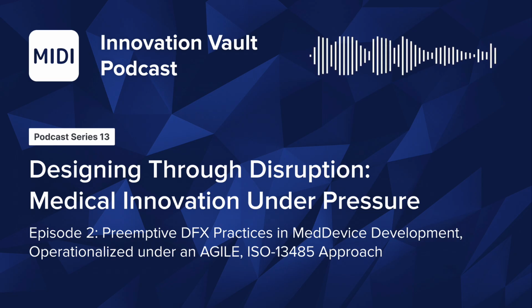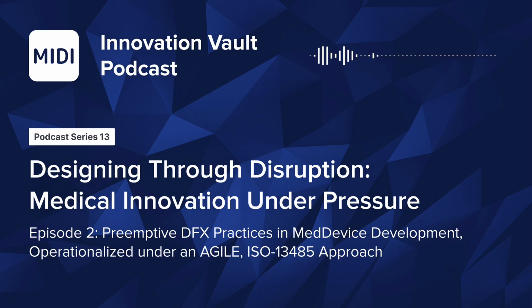The extended life cycle of a medical device is important to preemptively consider early on in its development. If DFX is not optimized in a design, this could result in hidden costs and poor functional performance. Most medical device development programs which MIDI deploys integrate a robust service approach into the design in a way that's passive, with minimal labor required by implementing an Internet of Medical Things approach, an IOMT approach. This allows for remote diagnostics and can often preemptively mitigate situations.